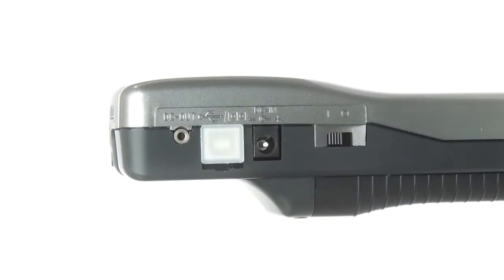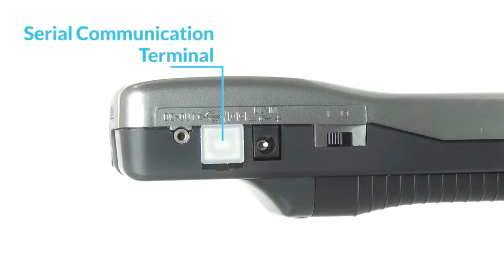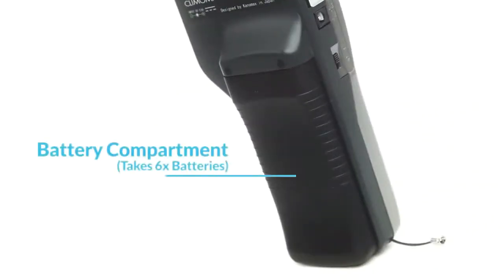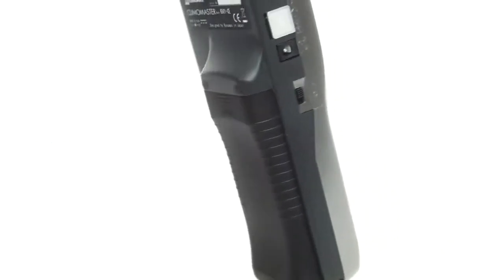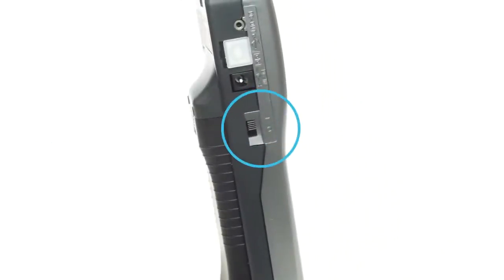The terminals and switches on the left side of the device are dedicated to data communications and power. Starting at the top, you have your analog output terminal for directly relaying measured data to connected analog devices. Below that is a serial communication terminal for interfacing with a PC via USB cable. The DC input terminal allows for continuous power when paired with the AC adapter. If you need to remain mobile, there's always the battery compartment on the back that can power the device via 6 AA batteries. When you're ready to power on or off the device, just flick the switch.